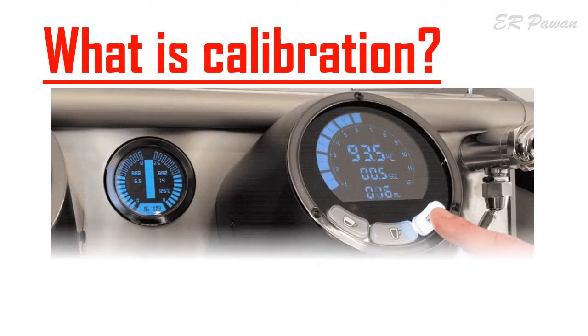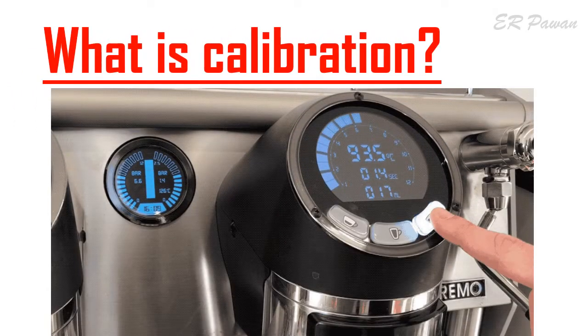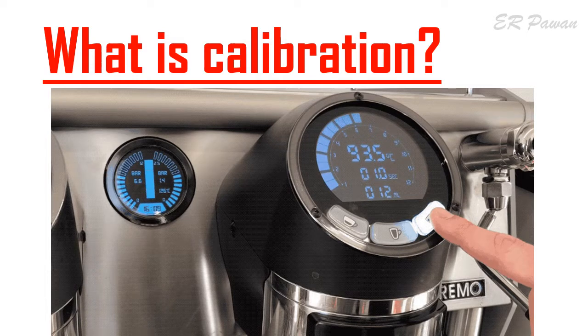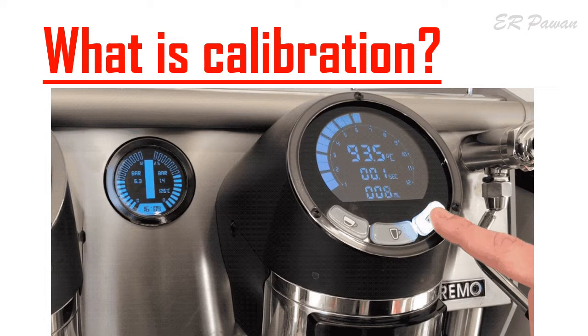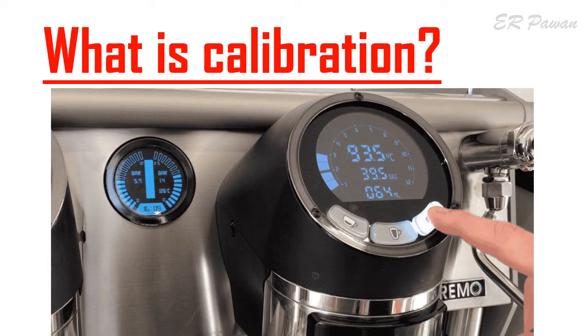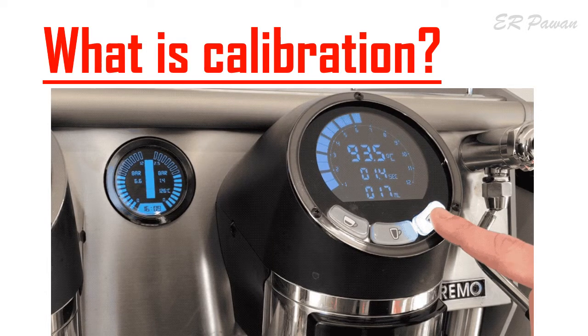What is calibration? In measurement technology, calibration is the process of checking the instrument with a standard instrument to improve the measuring functions. The accuracy of the standard device taken for calibration should be 10 times the accuracy of the measuring device.